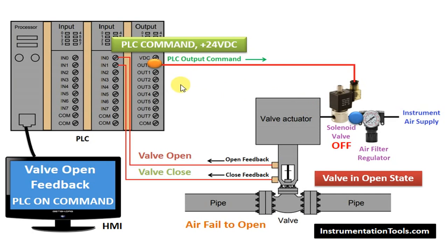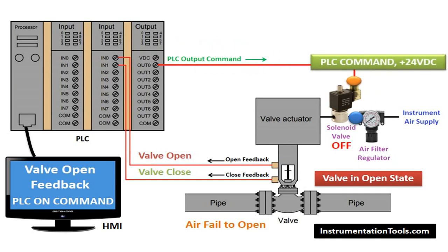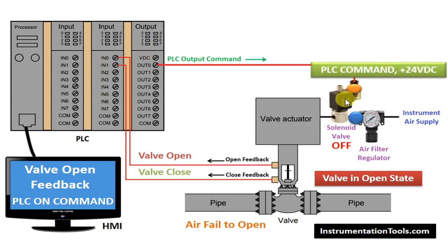PLC command is given. From the PLC digital output, the power will be sent to the SOV. From the output, the PLC command will go to the SOV. Nothing but PLC gives power supply to the SOV — in our case, 24V DC. Once 24V is received, the SOV is energized. In our example, the SOV is normally-closed type. That is why the input air is available to the SOV, but it will not send air to the valve while de-energized. Now, as the PLC has given the command, the SOV is energized and it will change state from OFF to ON.